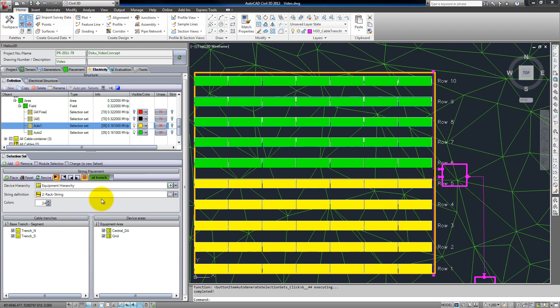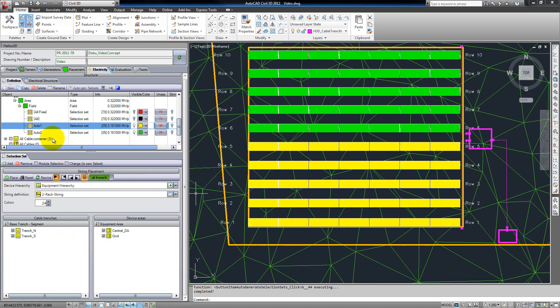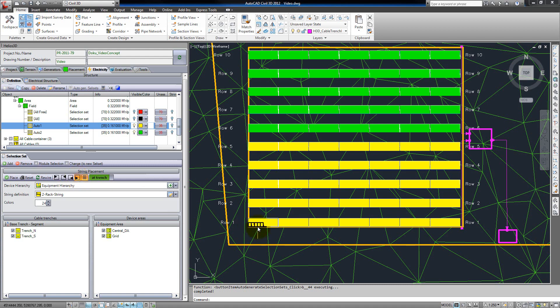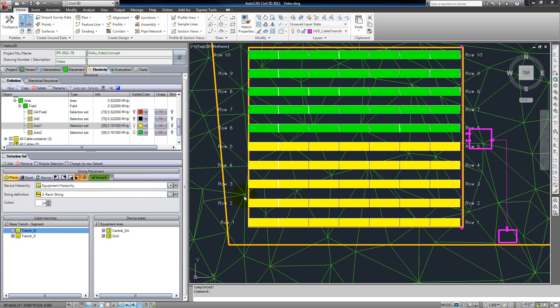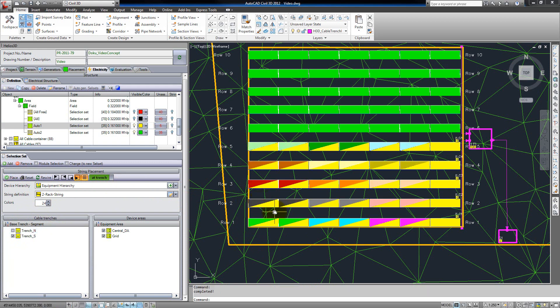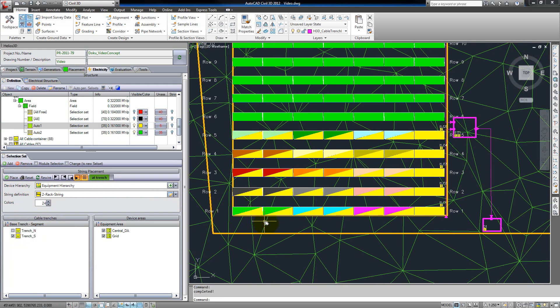Down here we can create a placement for any of these selection sets. The placement means the wiring beginning at the modules up to the grid connection. For our first selection set, colored in yellow, we start wiring at the left side and at the lower end of the module. We place our combiners at the trench, and we just want to connect to the southern cable trench. Now we say place, and we can see that the symbols for the strings are placed above the markings for our selection set.